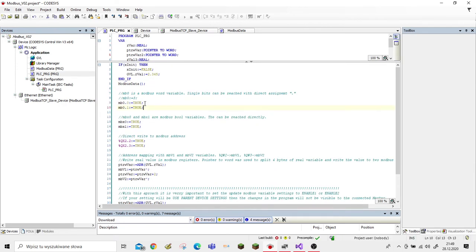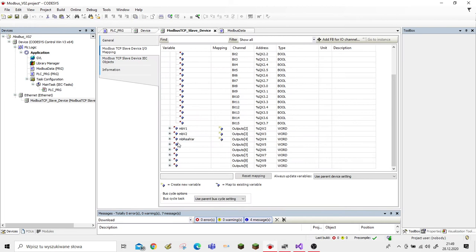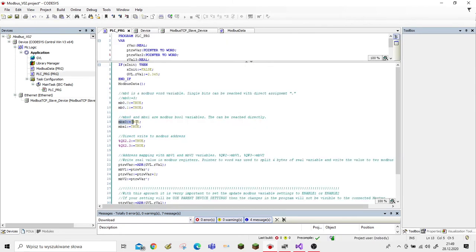Let's jump to PLC_PRG. We have to assign a value to a Modbus register variable. This is very simple — we assign the value, in this example 3, to mb0. We can also assign bit variables: if we declared a register mb0, to set a bit we use mb0.0 and mb0.1 and then assign the values. Another way is to declare bool variables and assign a true value.